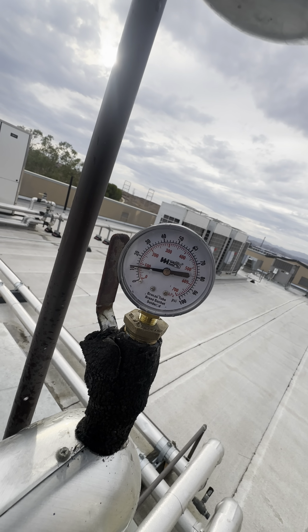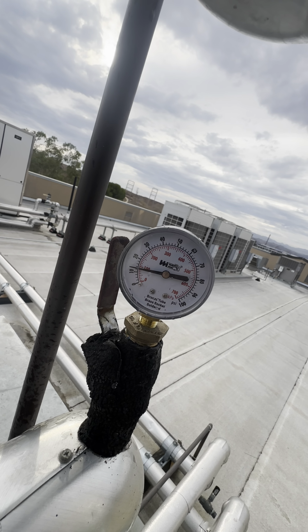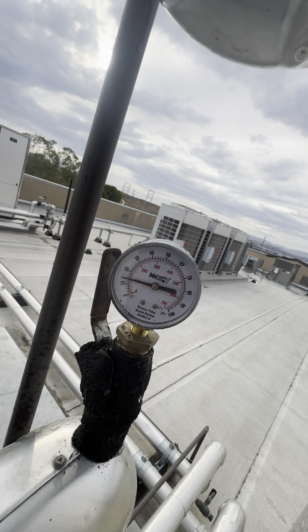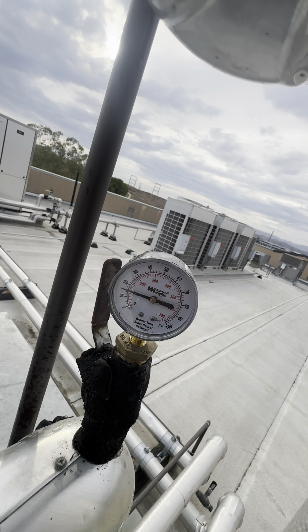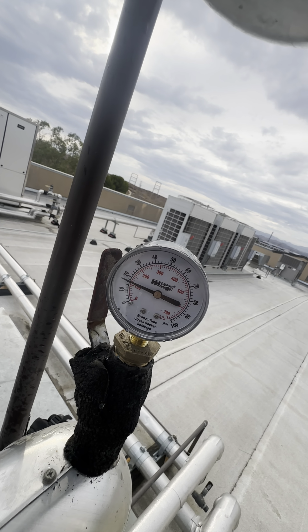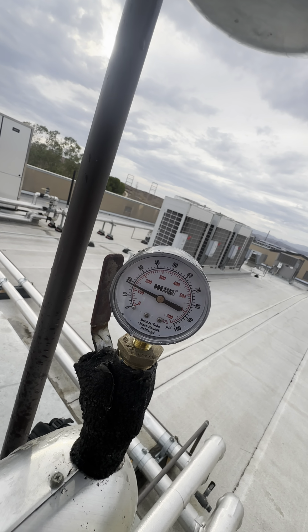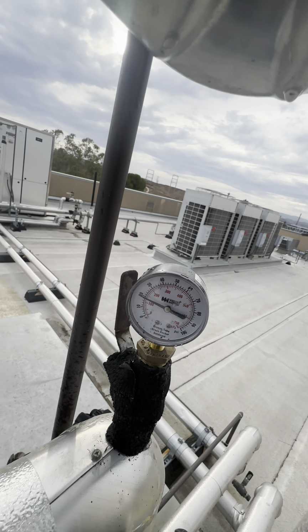And you can see we're increasing pressure. We're going to start at about 20 psi and then turn the pump on. That way we can watch our supply and return pressures from the pump. And after that, we'll go ahead and turn the chiller on.